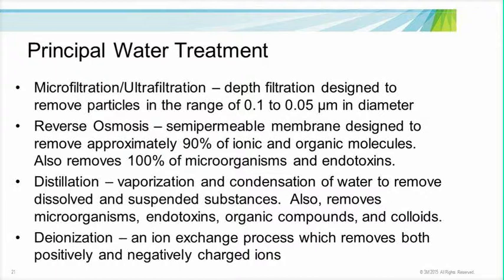Reverse osmosis utilizes high pressure to force water across a semi-permeable membrane. Perhaps the most effective filtration method, RO removes 100% of microorganisms as well as endotoxins and removes approximately 90 to 95% of ionic and organic molecules. The disadvantage of RO treatment is equipment expense, slow water generation, and low efficiency. By design, RO membranes only recover approximately 25% of incoming water.